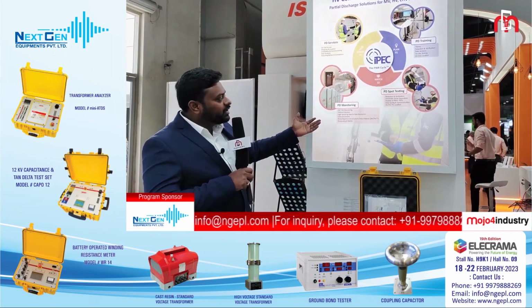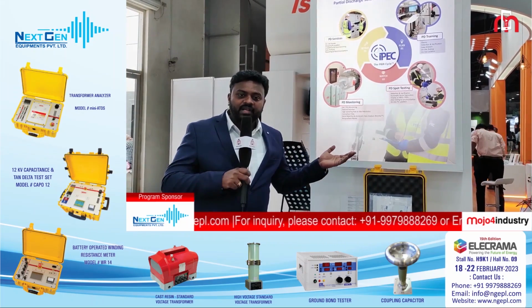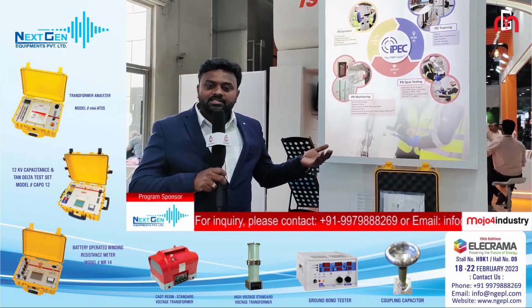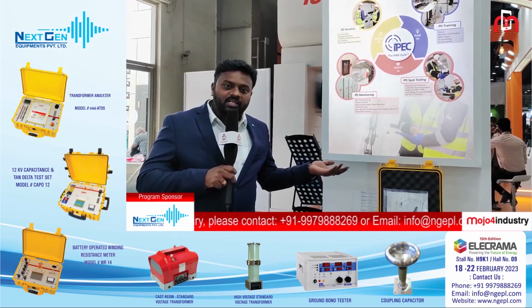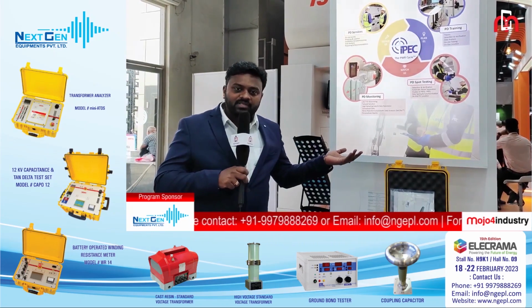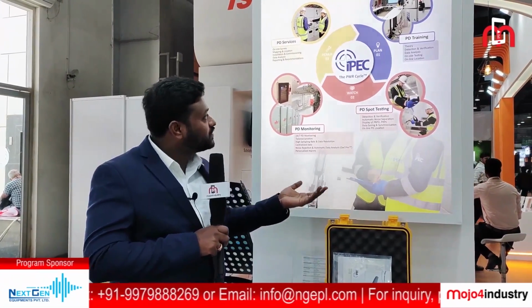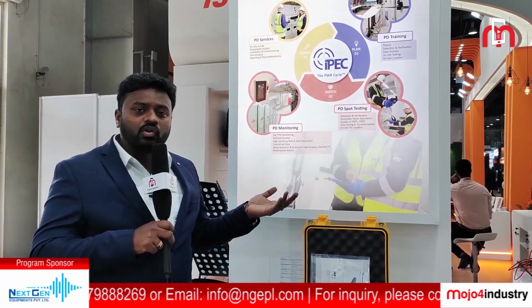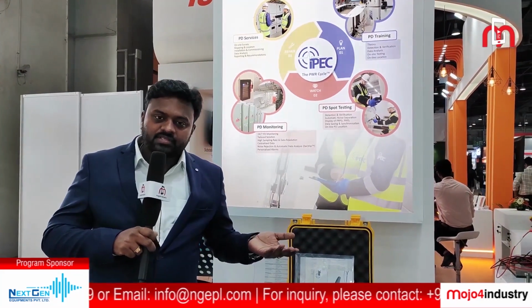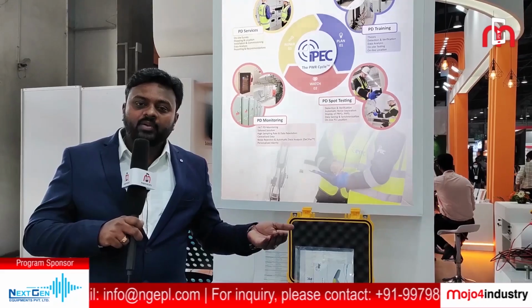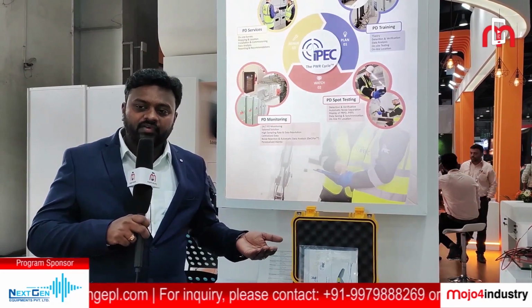Then comes continuous monitoring, which is 24/7 PD monitoring, where you get alerts on actual partial discharge activity through emails or SMS on a daily basis. Apart from that, we do a lot of PD services, including reporting, locating the partial discharge, and generating case studies for customers.